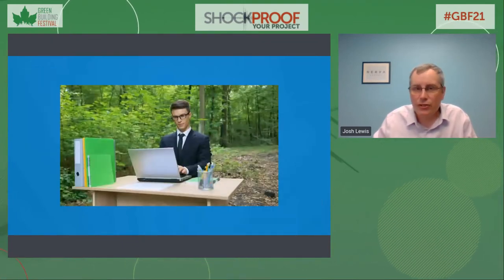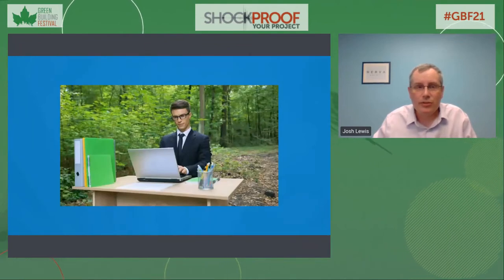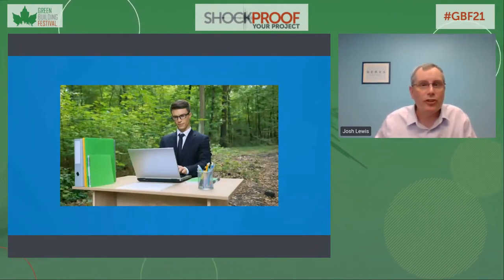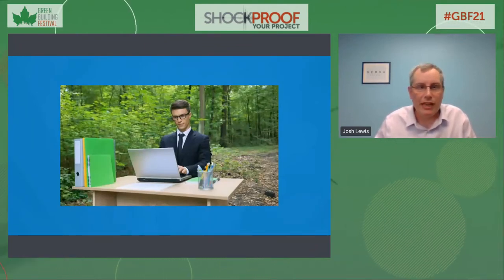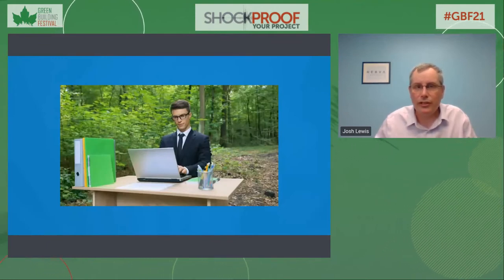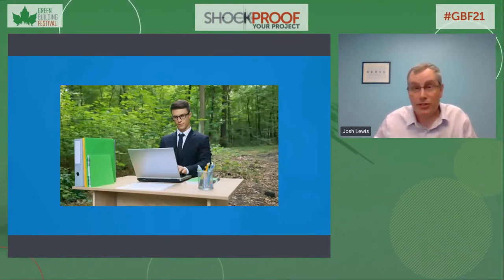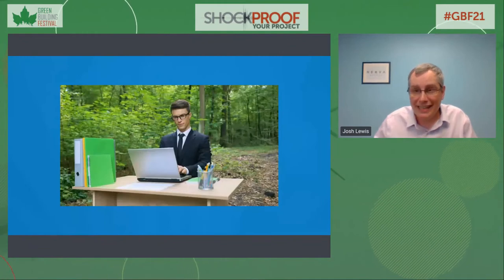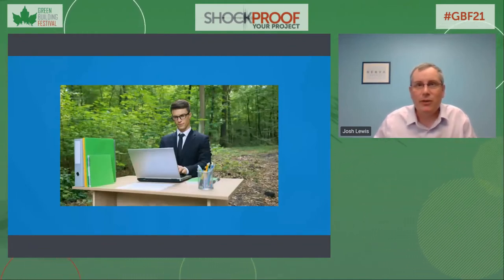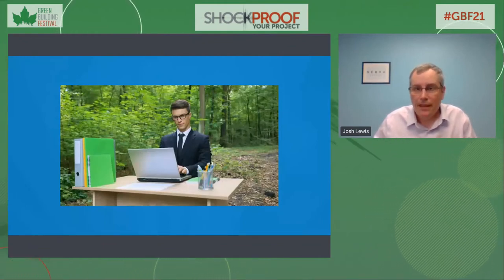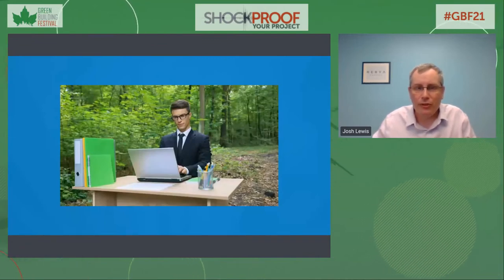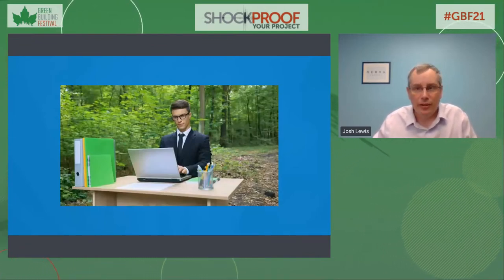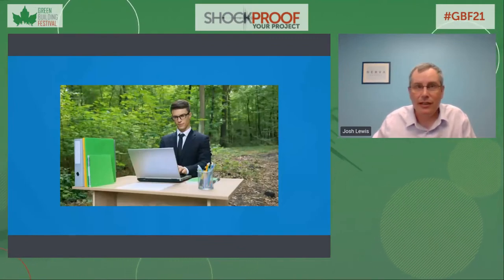To close out dilution, we also need to discuss the introduction of fresh air into buildings. Replacing a percentage of the interior air with fresh outdoor air helps dilute and expel contaminants, which may be causing indoor air quality issues. If we brought 100% fresh air into a building all of the time, the indoor air quality would be expected to be quite good. However, from an energy efficiency point of view, the amount of energy needed to run at 100% would be staggering for most buildings compared to their baseline.